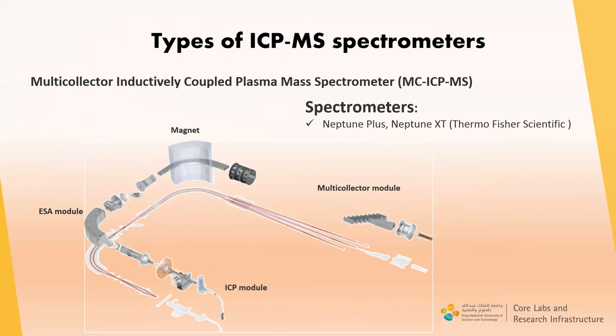The mass analyzer of the multi-collector ICP-MS spectrometer is also a double-focusing magnetic sector, but based on direct Nier-Johnson geometry — where the magnetic field is behind the electrostatic analyzer. In addition, a conventional detector is replaced by a multi-collector module, which allows simultaneous detection of elements. This type of spectrometer includes all the advantages of high-resolution ICP-MS, plus it extremely improves accuracy and precision of isotope ratio determination and decreases the time of analysis.